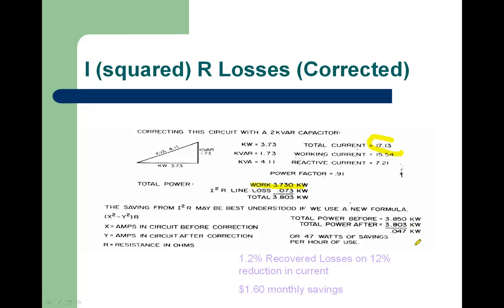So in the calculations that they've used here, it's 0.047 kilowatt, which is pretty low when you think about 47 watts. But if we look at percentages, it's about a 1.2% recovery on a 12% current reduction, and that would amount to about $1.60 in monthly savings. So there are actual kilowatt savings that can be made. I'm going to show you a little later. These things are sometimes very, very difficult to see on a hydro bill. You certainly can see the kVA reduction because it's in amps or kVA, but the kilowatt reduction would be very difficult to see on a hydro bill over a period of a month.